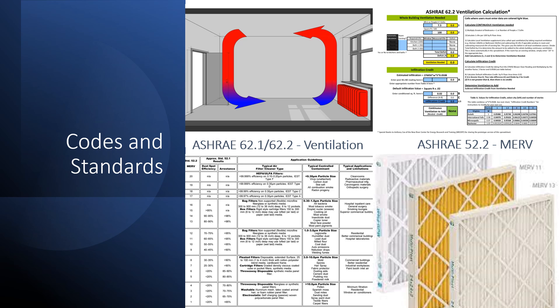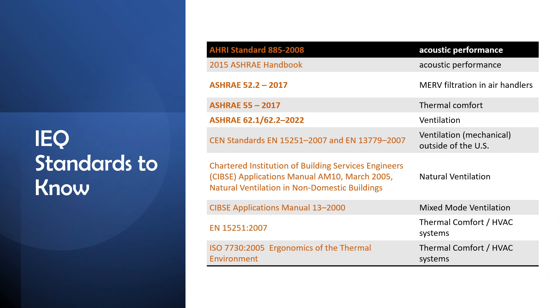Some codes that you absolutely need to know: ASHRAE 62-1 and 62-2 for ventilation. The main difference between 62-1 and 62-2 is that 62-1 is for commercial and institutional buildings, while 62-2 is for residential buildings. ASHRAE 52-2 is a method of testing MERV filters. You also need to add ASHRAE 90 for energy to that list. So, 52-2 is the method of testing MERV filters. ASHRAE 55 is thermal comfort — temperature, humidity, and airspeed. And 62-1 and 62-2 are ventilation.